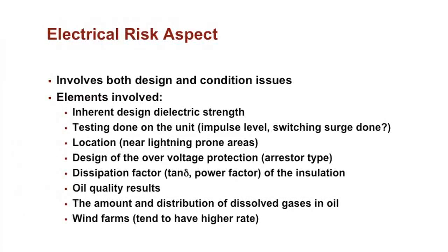Okay, so now we'll go to the electrical risk aspect. What we're looking at here is the strength of the transformer, that it can take some kind of overvoltage or a transient voltage. Normally you have an AC, sinusoidal voltage on a transformer. An impulse is something like when lightning hits a line and that voltage surge goes back to the transformer, and that has a very distinct wave shape. Then you can also have what you call a switching surge, some kind of switching fault, and that has a very different wave shape.